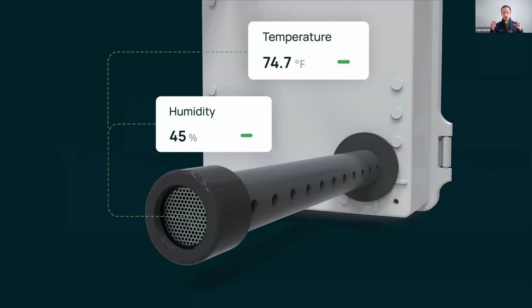Answer is simple. Certain sensors are located directly within the airstream inside the duct itself, and that gives us sub-second response times for those parameters directly from within the airstream. Now, other parameters that benefit from a more stable pressure environment, those are measured within that sealed chamber. And we've tested this across an extremely wide range of air speeds, duct shapes, duct sizes. It works.